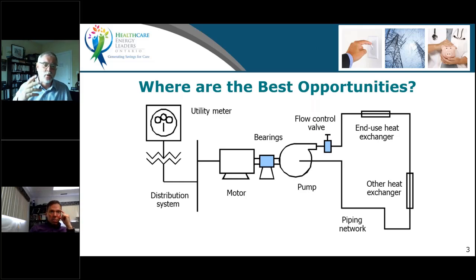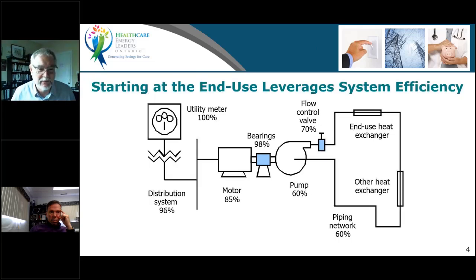And I always like to say, where are the best opportunities? Well, I'm going to argue the best opportunities are deep down in the system, and I'm going to show how we do that. The next question I'm going to ask you is, what's the overall efficiency of this system? Going from electricity at that meter, all the way over to water power, which is really to overcome the pressure difference between those two heat exchangers and move fluid properly to carry heat. So what's the overall efficiency of that system? Or how do we calculate it?